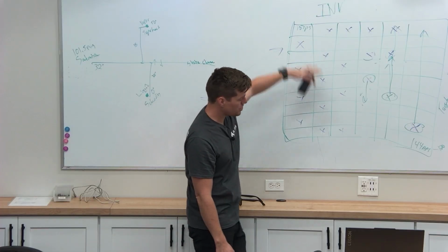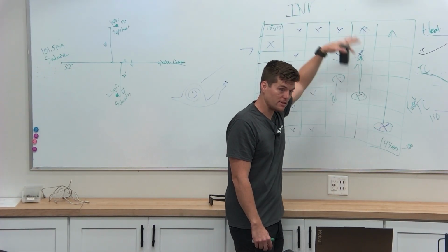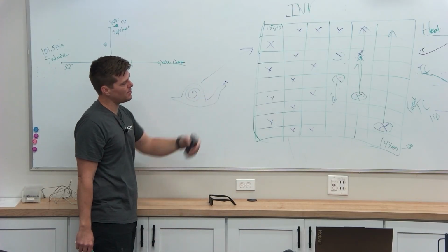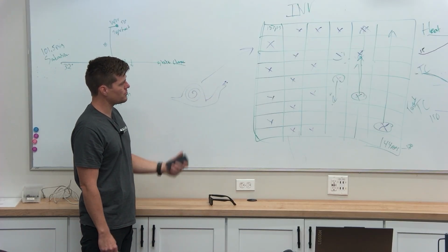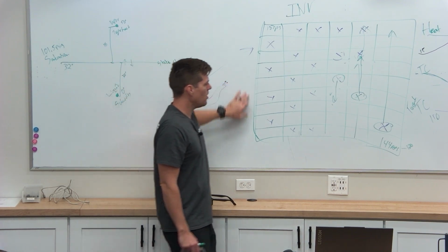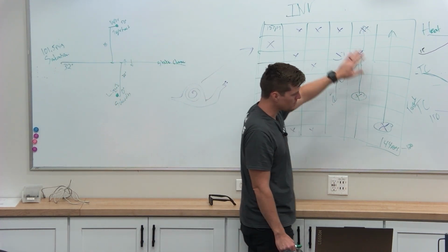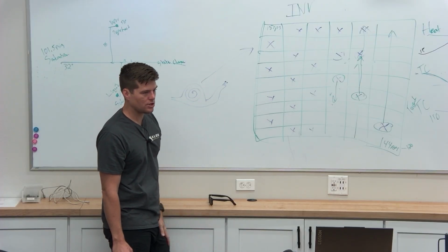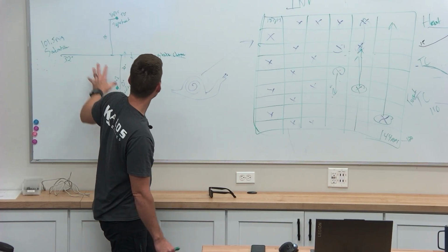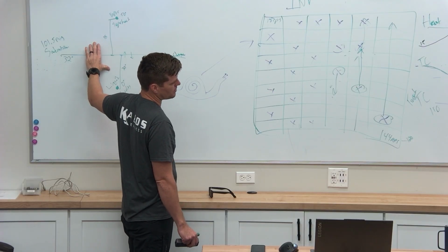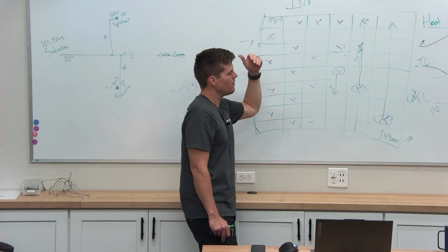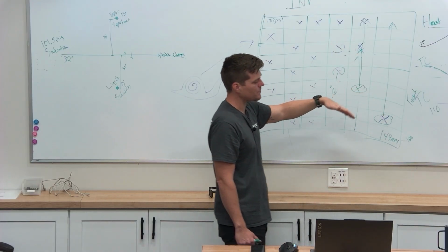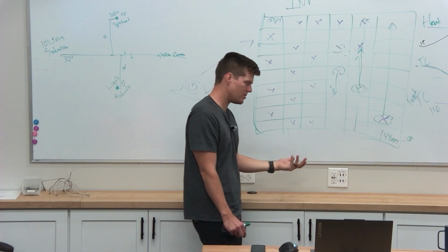These are just the basic modes of control. This is the sheet that it's working off of. This is how it uses those numbers and how we have access to those numbers. And that's the basic mode of control for controlling compressor speeds. So it's not only looking at what speed am I at, but also what is my discharge temperature, what are my speeds actually at, how do they correlate to each other, all those things together. But all that comes back to saturation temperature, for your evaporator line, for your condensing line, your condensing temp, your discharge line.